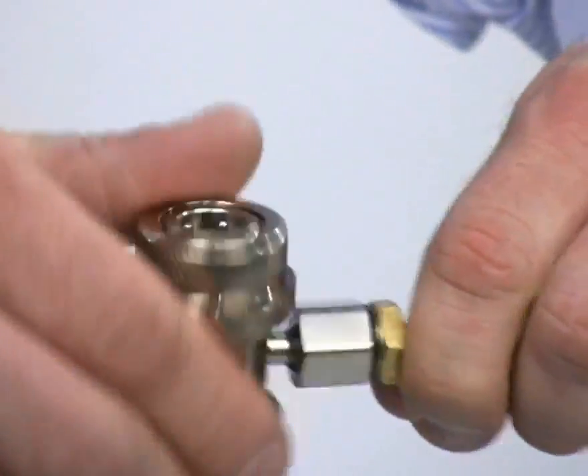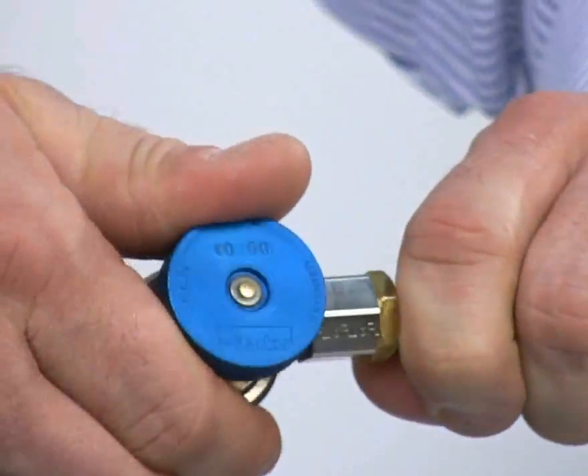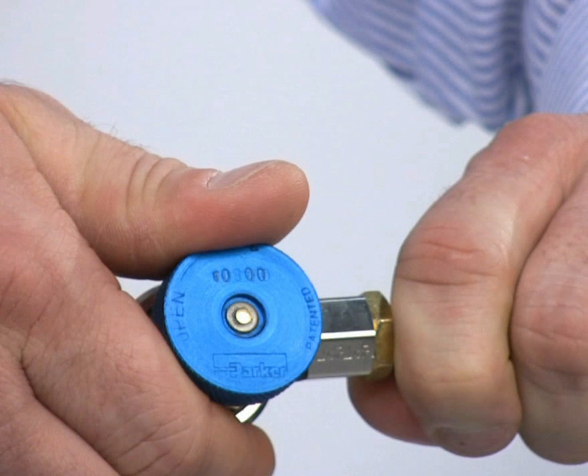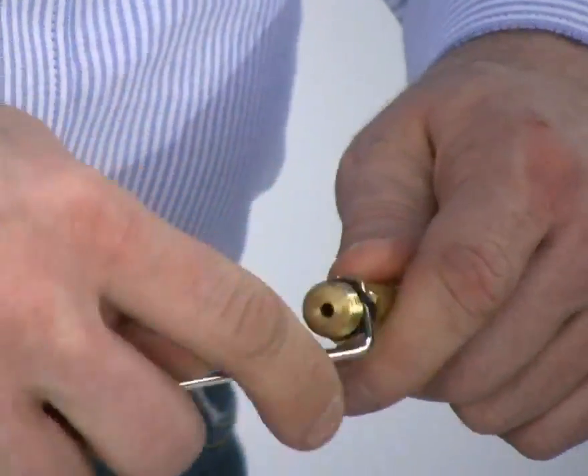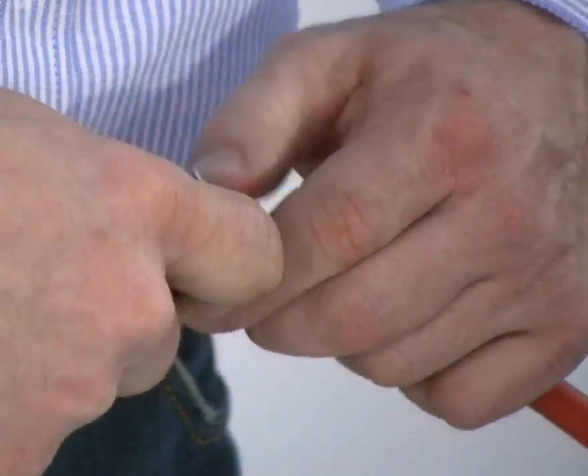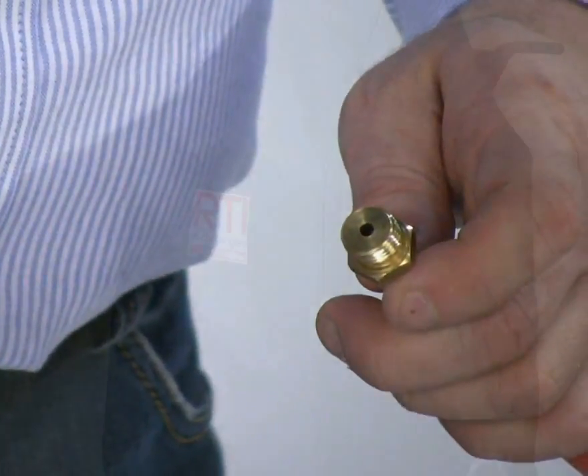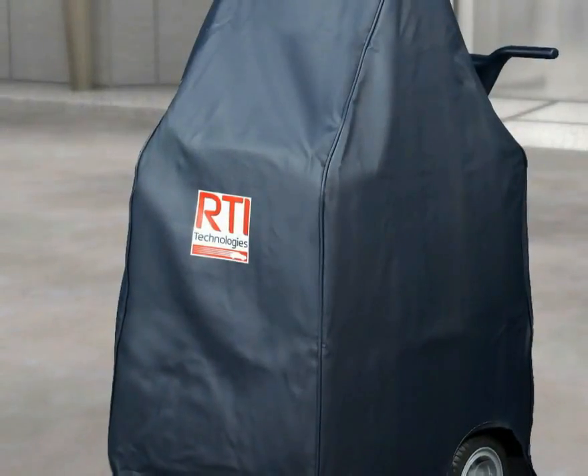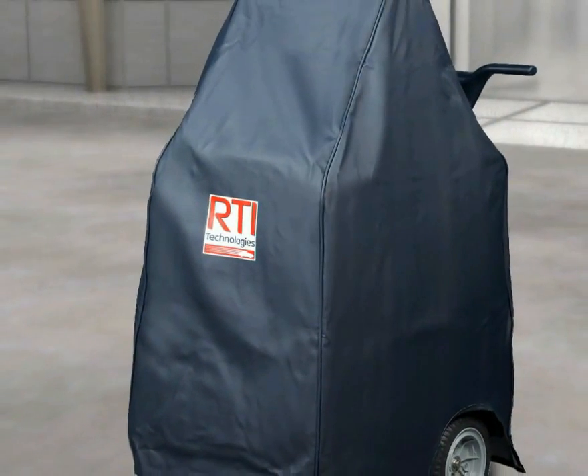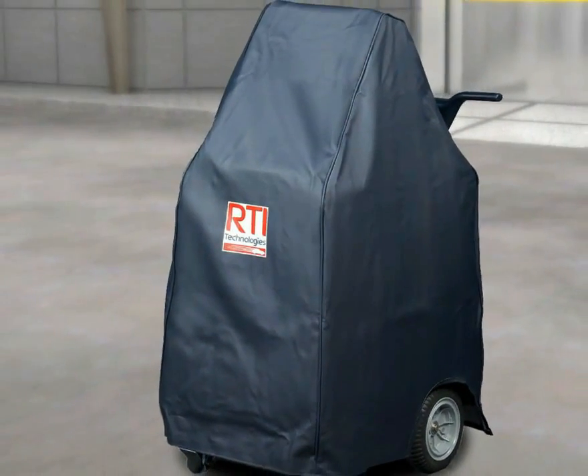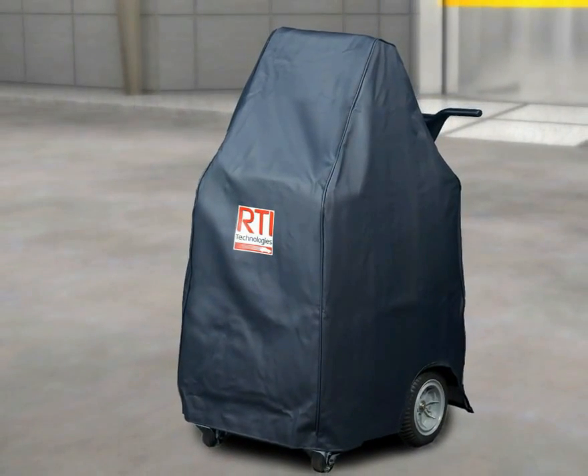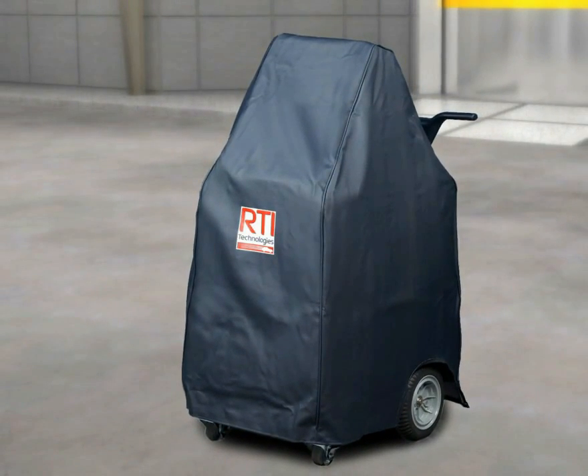However, they do require frequent inspection to ensure mating surfaces are free of contamination and debris, and it is important to inspect them before every service to confirm proper gasket condition for adequate sealing. All service couplers utilize O-ring technology for proper service hose sealing, so replacement doesn't require special tools. Now let's focus on the optional RHS980 shop cover. All Arctic Pro shop covers are manufactured from the highest grade vinyl fabric to ensure long wear and the utmost endurability and abrasion resistance. Each cover has finished expansion slits with Velcro closure pull tabs to ensure a secure fit.